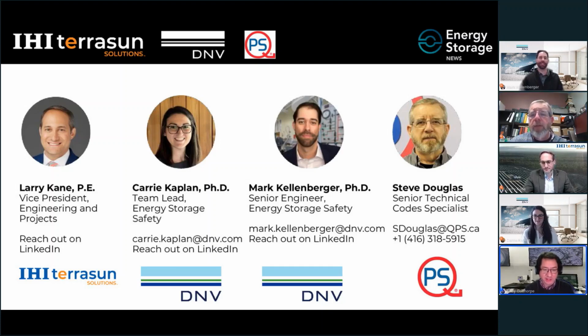Okay, anyone else? Yeah, I can take that. So UL9540 is definitely separate but works with NFPA 855. 855 is its own standalone standard that has to be followed. As part of UL9540, one of the requirements for a 9540 listing is compliance to 855. So to get the UL9540 sticker on your project, you have to show you meet all applicable requirements from NFPA 70, the National Electric Code, from NFPA 855, which includes compliance to NFPA 68 or NFPA 69, and also the International Fire Code and many other standards. So they go together, they are separate, and to meet 9540 you have to be compliant to 855.